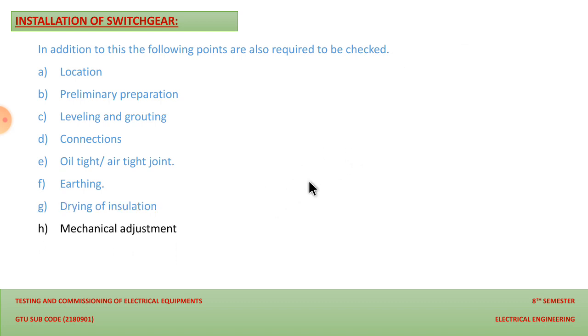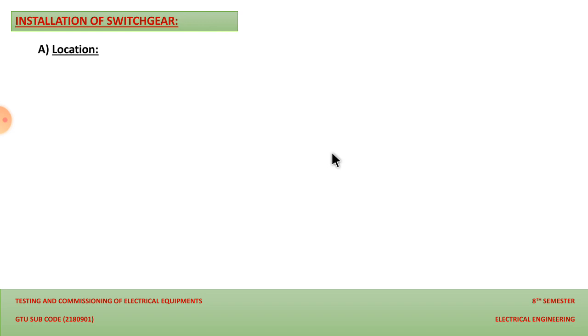And the mechanical adjustment, which is necessary while we are installing the switchgear. And provide proper isolators while we perform operation and maintenance. This is a main parameter. Through the isolator we can disconnect our circuit breaker for further operation and maintenance, so we have to check that before installing the switchgear. And then the level of oil and the requirement of oil for the operation, we need to check while installing the switchgear. So let us discuss all these points of switchgear installation in detail.